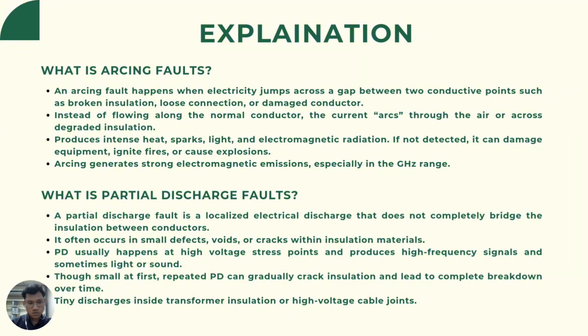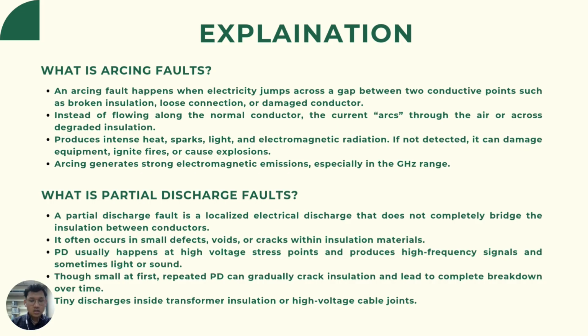So, what is an arcing fault? An arcing fault happens when electricity jumps across a gap between two conductive points, such as broken insulation, loose connection, or damaged conductor. Instead of flowing along the normal conductor, the current arcs through the air or across the insulation, producing intense heat, spark, light, and electromagnetic radiation. If not detected, it can damage equipment, ignite fire, or cause explosion. Arcing generates strong electromagnetic emission, especially in the gigahertz range.